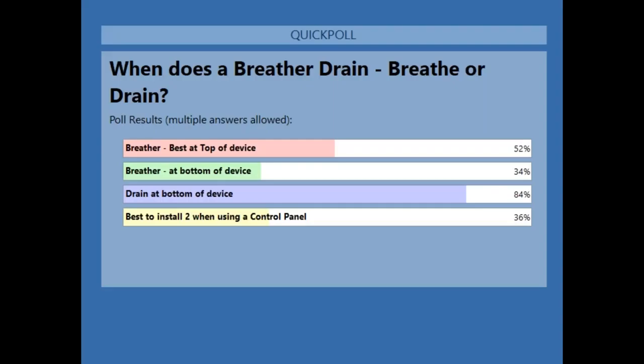Now, all answers are correct, but perhaps do not put the breather on top of the device; put it up at the side at the top. That would be the most ideal location for a breather, because when it's hot, you want it to exit the box. Of course, you also have to install one at the bottom, because that's where it's going to drain if any condensation does get inside. So actually, all answers are correct, but it's probably best to install 2, one at the side at the top and one at the bottom at the lowest point.